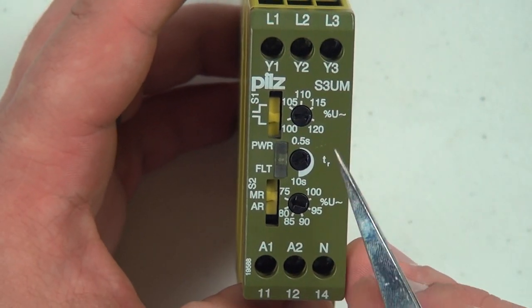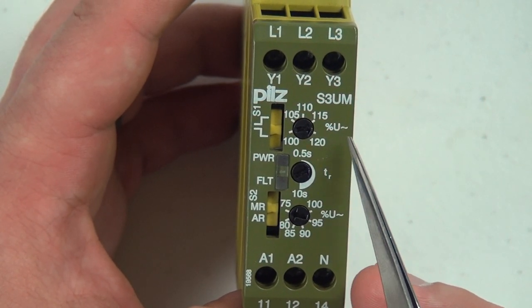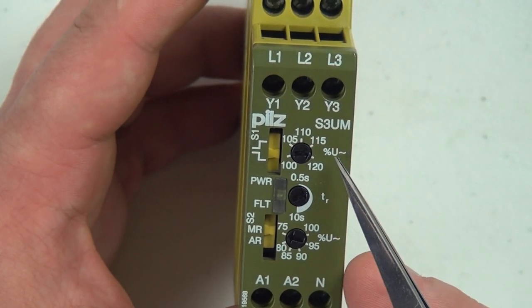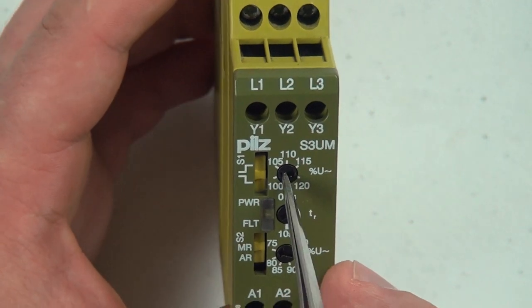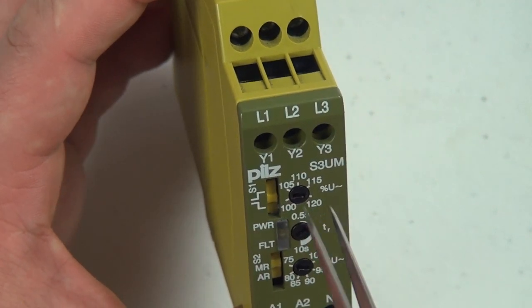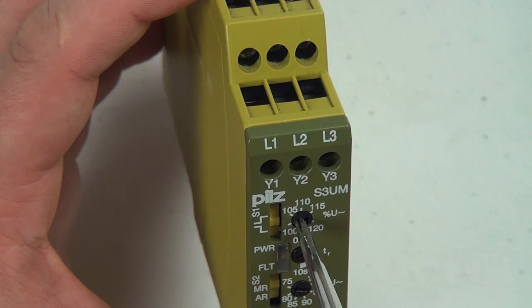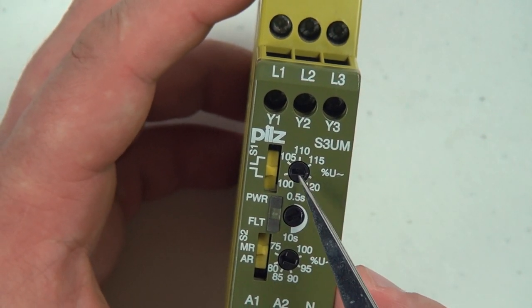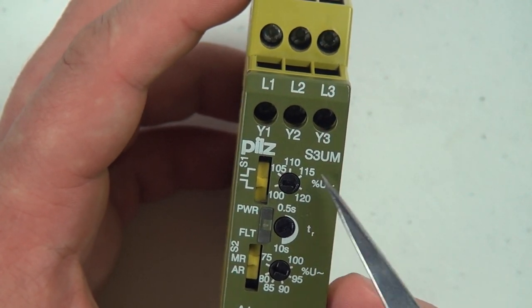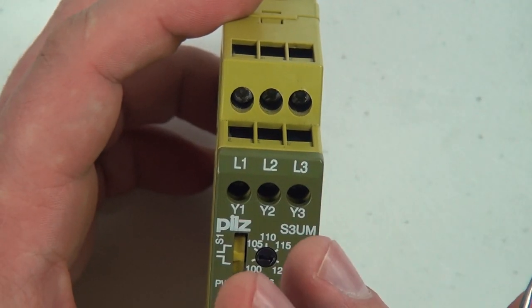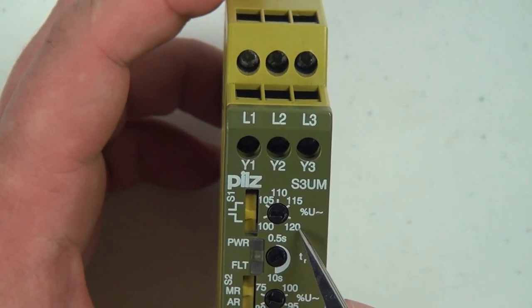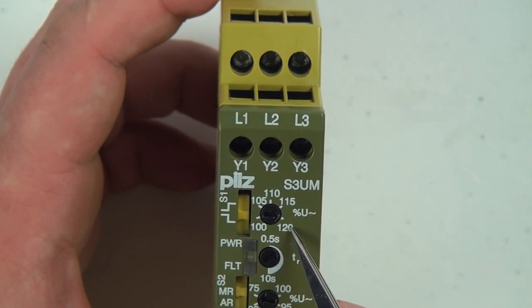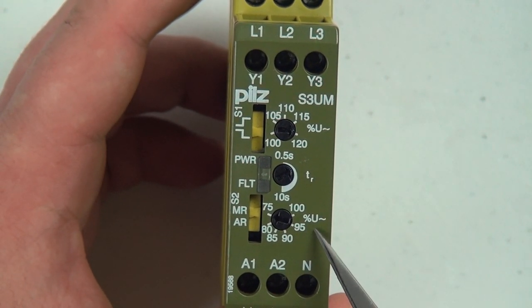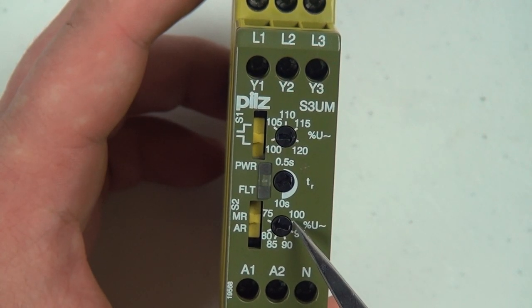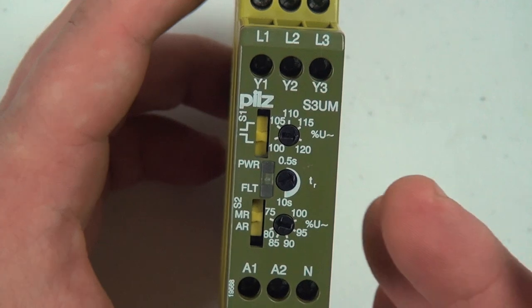Also on the front panel here, as you can see, these right here are your voltage levels. So this one right here is your overvoltage. And so if we can turn this little arrow, well, it's kind of hard to do with tweezers, but anyway, you can turn this arrow and select whether you want your overvoltage to be 100%, meaning that if you exceed, let's say, 400 volts, immediately the relay will detect a fault. Or you can go as high as 120%, which would be, I think, 480, and the relay still won't care. And similar to the undervoltage, you can have 100%, or you can have 90%, 80%, 75%.